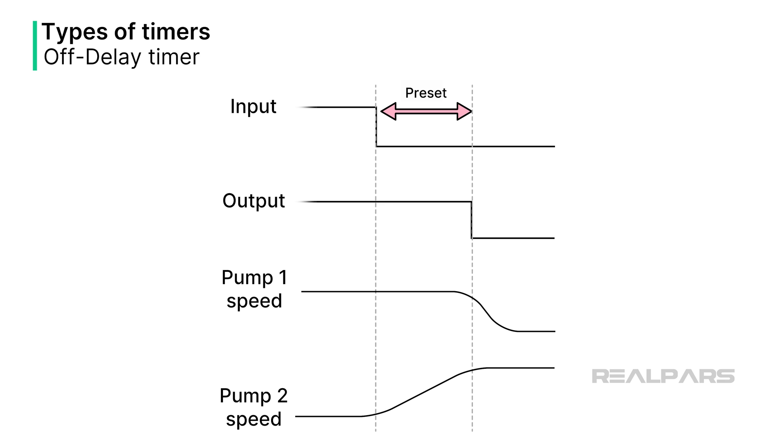When transferring operation from a primary feed pump to a secondary feed pump, an off-delay timer can be used to delay off the primary, while the secondary has a chance to ramp up to speed. This keeps the primary pump on for the preset time, preventing a loss of flow during the transition period.